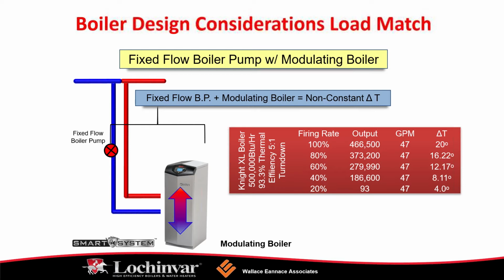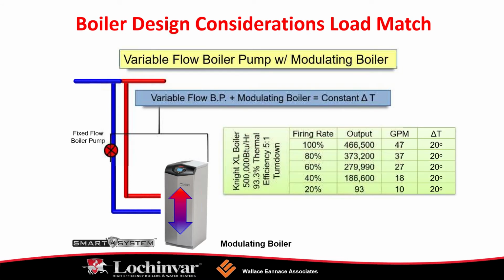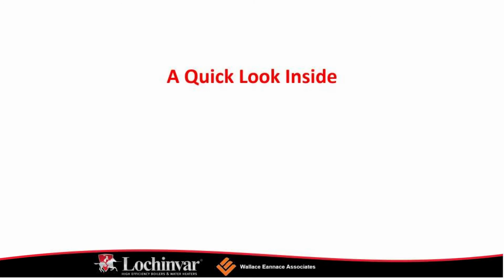A full flow system can reduce installation costs by eliminating the need for primary, secondary piping and pumps. We're maintaining consistent delta T throughout modulation range with our variable speed boiler pump. Reduces boiler cycles. That's a picture of a Bell & Gossett EcoCirc pump.